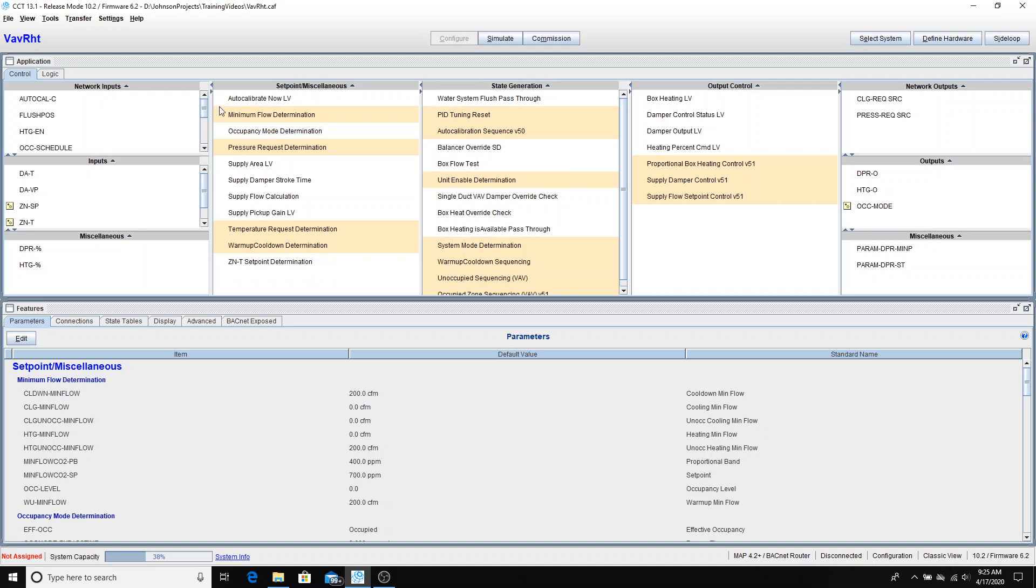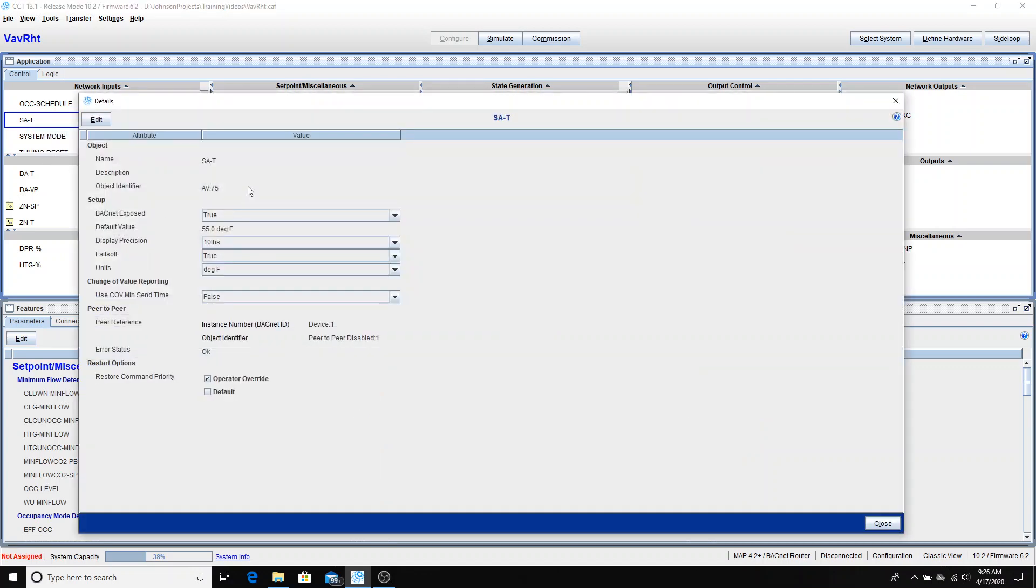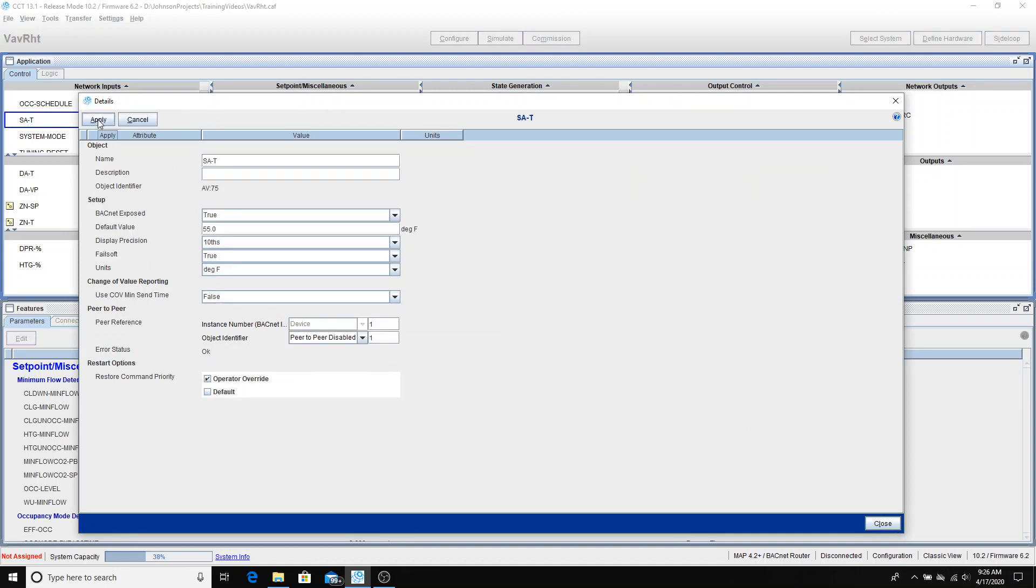So first thing I want to look at is this SA-T point on the network inputs. That is the point that's going to be monitoring the discharge air temperature from our air handling unit. So I'm going to go into edit mode on this. Go to view details. And I'm going to edit.